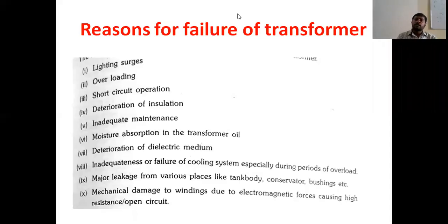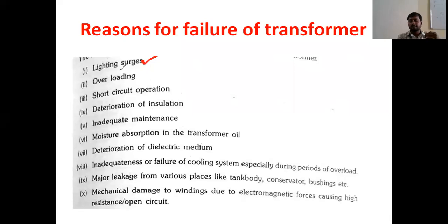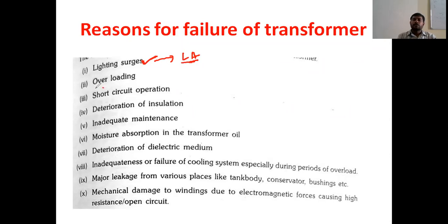What are the reasons for failure of the transformer? The first one is due to lightning. During the rainy season, because of the thunders, lightning will take place. If the lightning falls on the transformer, definitely the transformer will fail. To avoid this problem, we should use lightning arresters to protect the transformers.